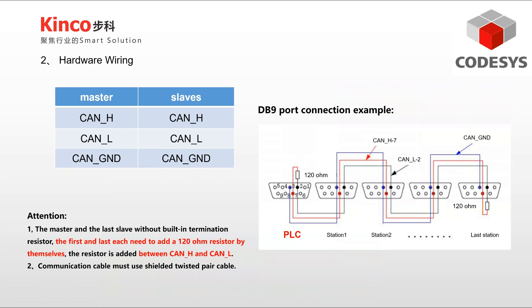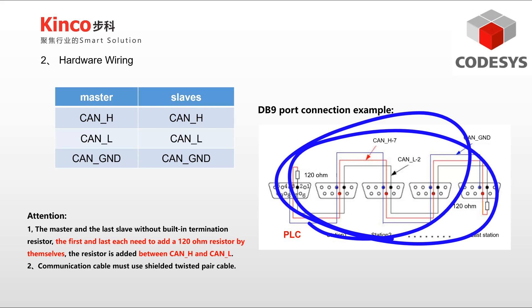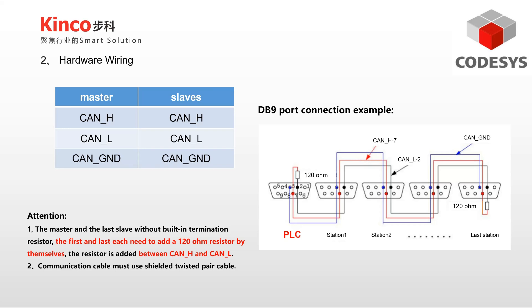The hardware wiring of the servo is CAN-H to CAN-H and CAN-L to CAN-L. CANOPEN communication requires a 120-ohm resistor to be connected to both the first and last nodes. As you can see in the figure, the right side shows the connection of the DB9 type interface.